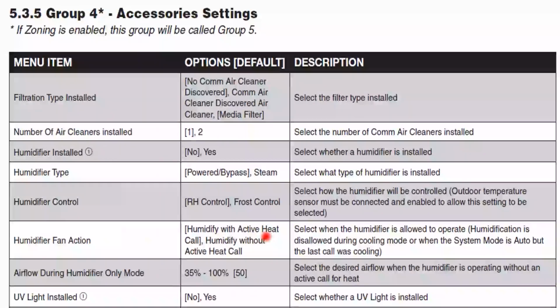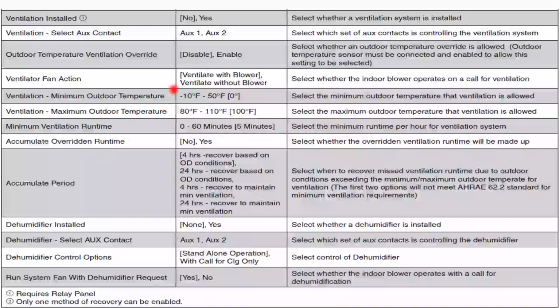Do you want the humidifier to come on with a heat call? Airflow during humidifier mode, so we can change the percentage of airflow. Again, you cannot change the percentage of airflow if you do not have the BK jumper for the S9V2. So keep that in mind. You have to have that BK terminal wired in to be able to control the percentage of fan. Is there a UV light installed? This is accessories, continued: ventilation installed.